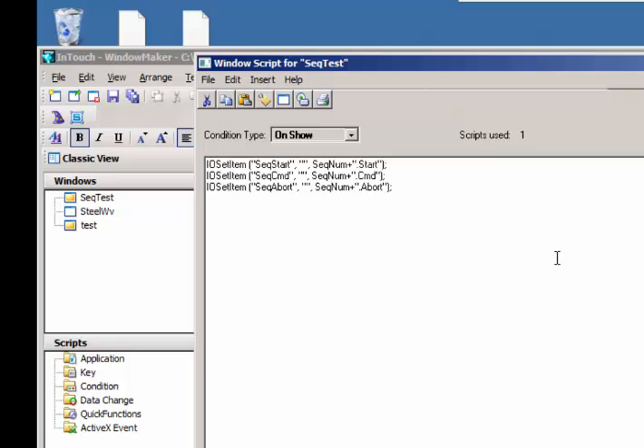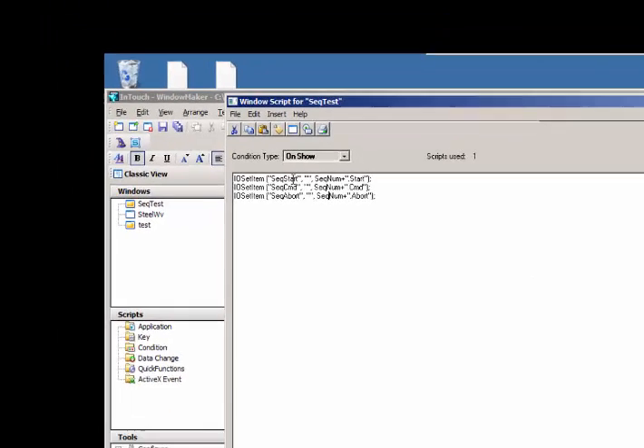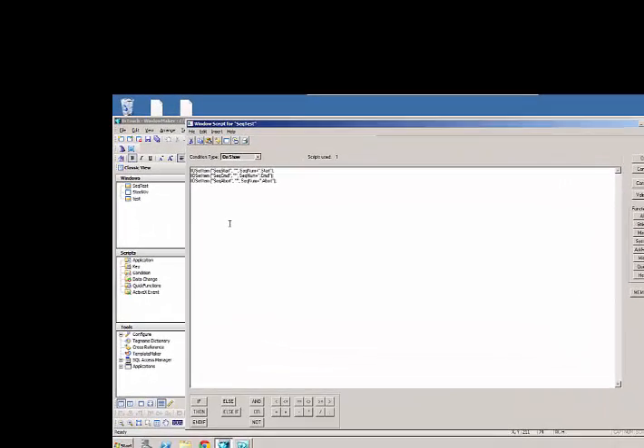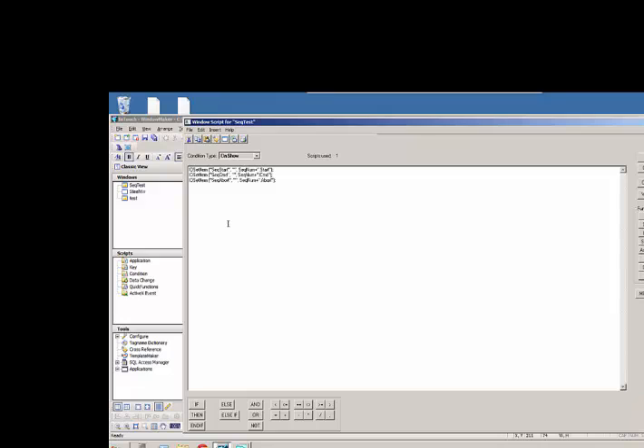So just a very quick little script here, I can use the same set of tags, the same three tags, sequence start, sequence command, sequence abort, use those same tags over again. I'm basically passing in the name of the sequence number, and then I'm using this to set the address of the variables so it points to a different set of variables in the PLC.